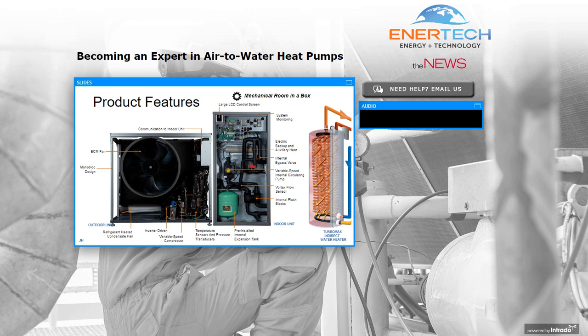It's a monoblock design, so one of the best things about that is we don't have any refrigeration piping. We're just running water piping, whether it be PEX or copper, from the outdoor unit to the indoor module, which is in the center of the slide here, and what we're calling the mechanical room in a box. So you can see in the center of the slide an expansion tank. There are actually flush ports, so we're able to purge air from the system. Variable speed internal pump. We have either an electric backup heater. There's an immersion heater, that's that gray bar in the center of the screen. Or we can go with dual fuel and energize a boiler for backup.